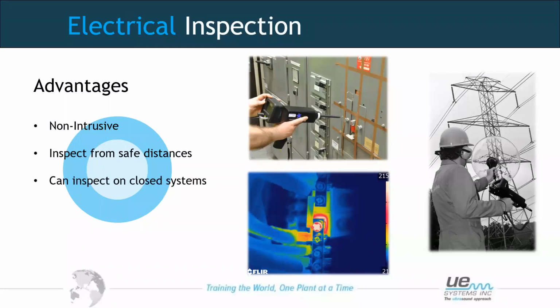So advantages of using ultrasound for electrical inspection are things like it's non-intrusive. We don't have to have eyes on the assets to be able to take readings. We can use the contact approach to listen to what's going on inside the cabinets. We can inspect from safe distances using airborne ultrasound. As I was saying, we can inspect closed systems, again another safe approach.